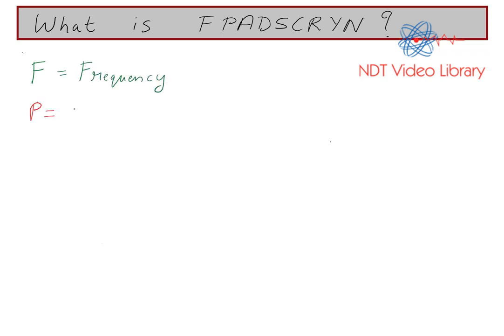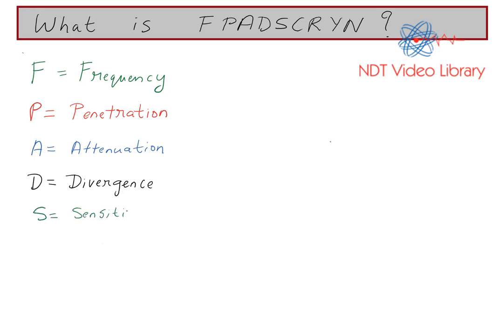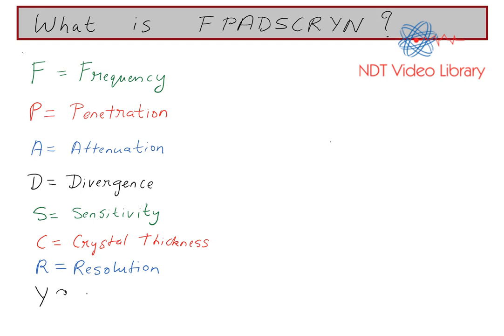F stands for frequency, P stands for penetration, A stands for attenuation — loss of sound — D stands for divergence, the spread of the beam, S stands for sensitivity, C stands for crystal thickness, R stands for resolution, Y if you invert it looks like lambda, which stands for wavelength, and N stands for near field.